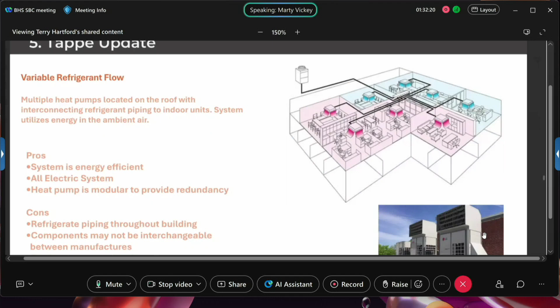That gets a little bit more of a concern with some changes coming up to the new refrigerants. There's some other safety precautions that have to take place when you have refrigeration within the building. So that's a concern that we want to make sure we address and that everyone's aware of. The other item for this system is the components are not interchangeable between manufacturers. So if you start with a certain manufacturer and you have equipment replacements required in the future, you most likely would have to stay with that particular manufacturer throughout the life of the system. And again, this system does take roof space, so we need to coordinate with PV systems that are available.